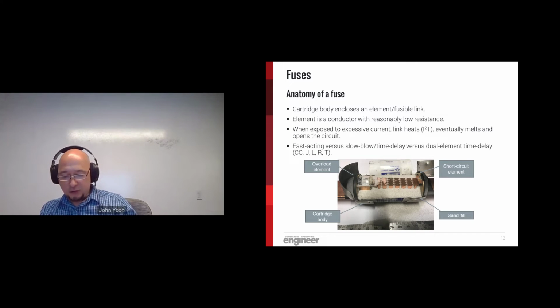So let's take a closer look at how a fuse works. Under normal operating conditions, that element has reasonably low resistance, so it is functionally no different from any other conductor. However, in an abnormal operating condition, we depend on a sacrificial element. We either have to melt or vaporize that element to open and interrupt the circuit. If that happens in free air, the act of melting an element and releasing that energy, in and of itself, could be potentially dangerous. As such, we have to somehow contain or dissipate that energy.